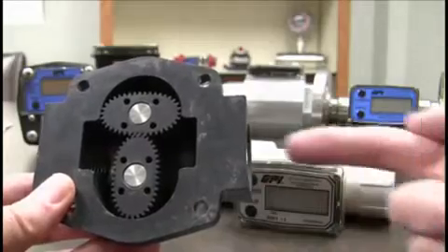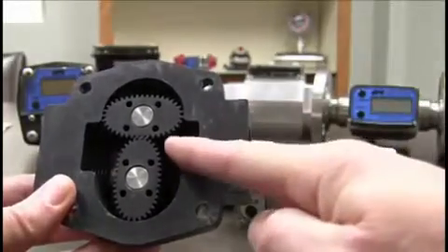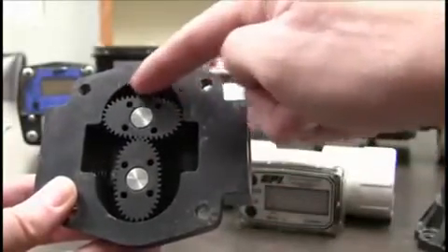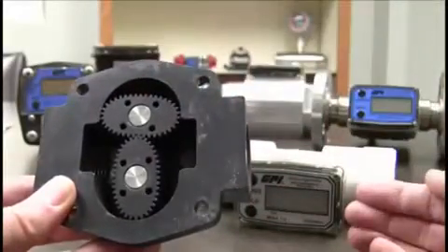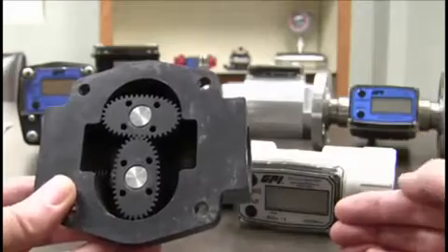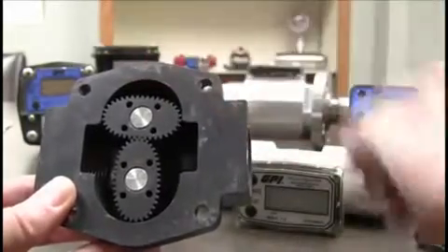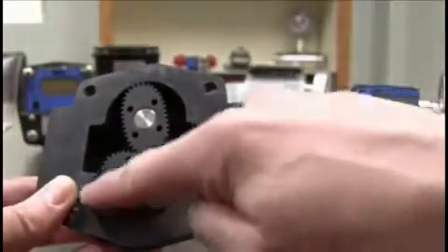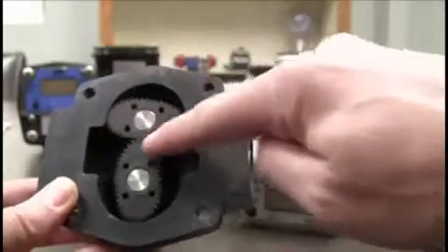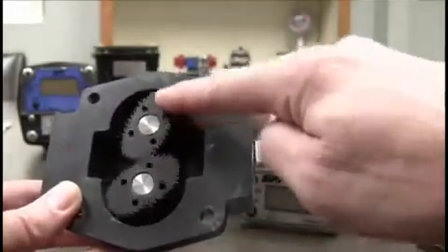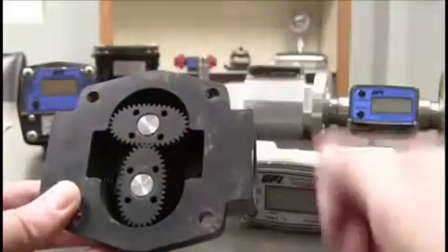So if you have your fluid coming in this way, it's going to come in through here. And you get a little chamber of the fluid right there, and that chamber never changes size, so it doesn't matter if it's thick like oil or thin like water, that chamber always holds the exact same amount of fluid. So it goes through and pushes out. At the same time, on this side, another one's going. So it just keeps going, and so really the fluid's going this way. It looks like the rotors are spinning backwards, but it pushes the fluid right on through and counts it.